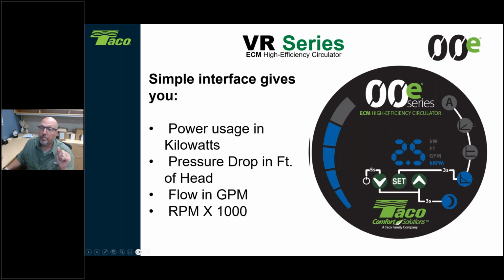The third one up here, all right, this is going to be our proportional pressure mode. And this is when you have, say, a thermostatic radiator valve, some valves that are constantly modulating. And last week, we did show you several piping applications that would use it with open-close valves, where you've got that extended header that runs throughout the building itself, and you have those open-close valves. So now we have a proportional pressure. And then the one at the top here is giving us that automatic mode, all right? And the auto mode, what we call Auto Adapt, is now taking into account the proportional pressure and figuring out which curve it's going to operate on. Here, you're programming that curve.